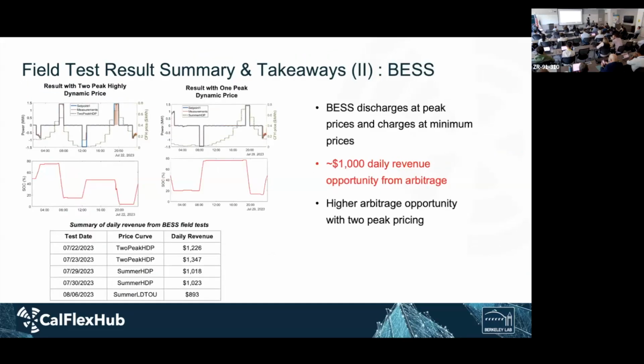This is the test result of the battery energy storage system. Quick summary: this is the test result with a two-peak price signal and a one-peak signal. The blue and red lines show what the MPC is doing - when the price is low, it tries to charge; when the price is high, it tries to discharge to reduce the load. You can check the charging and discharging by looking at the state of charge of the battery here. One key result is around $1,000 revenue per day because of the size of the battery energy storage system.